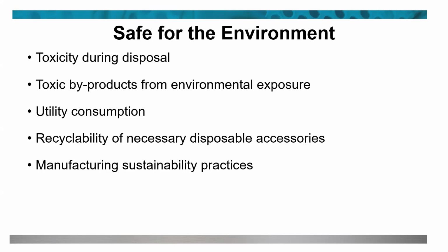Ethylene oxide, it requires emission scrubbers to prevent ethylene oxide from venting into the atmosphere and reacting with water to form substances like antifreeze. We also want to remember that some of these accessories may require special containers for safe disposal. So these are things that we want to look at.